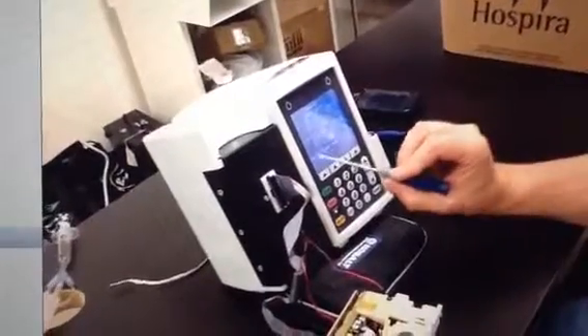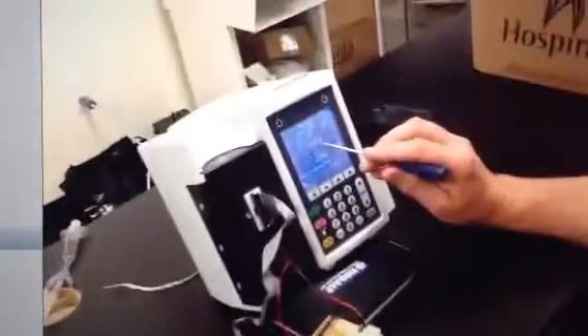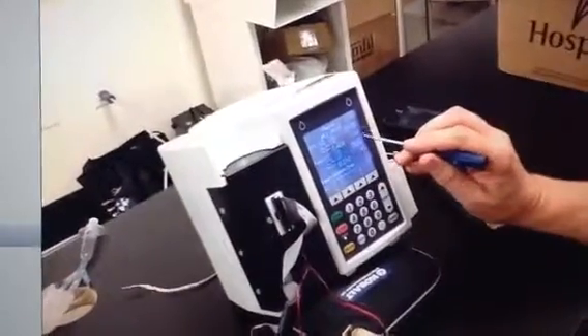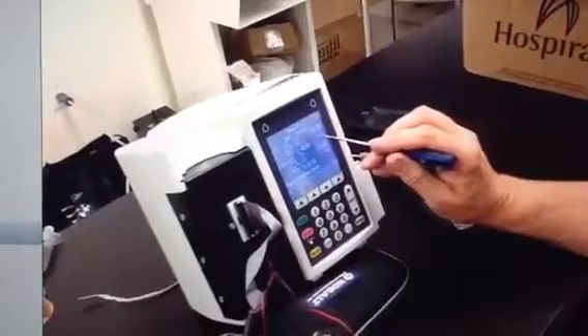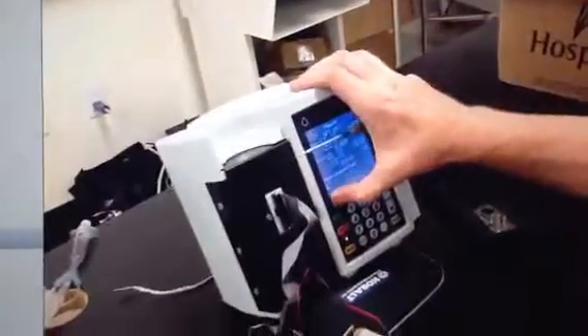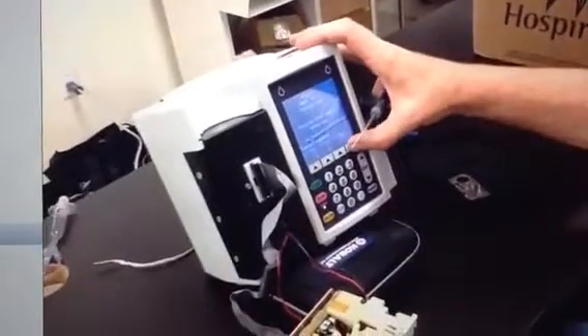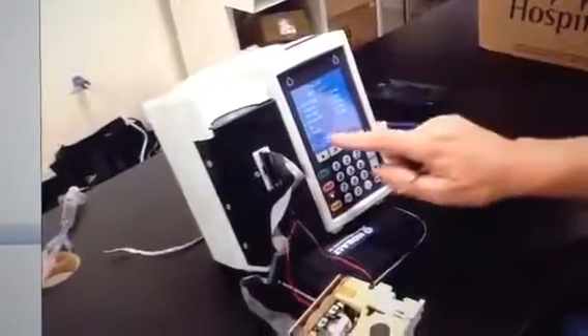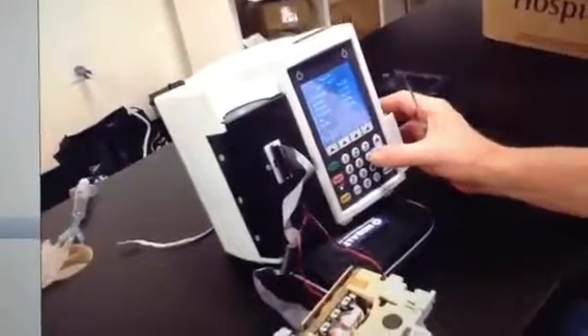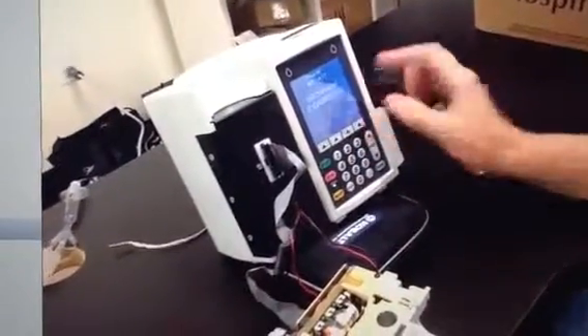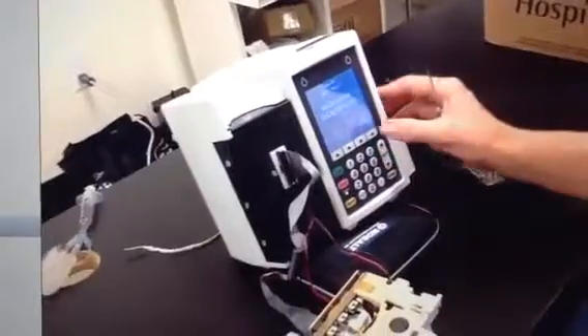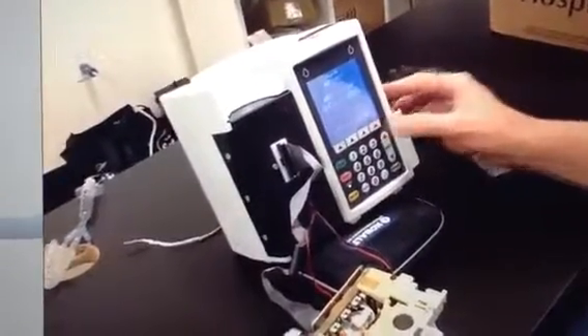Now it asks us to open the cassette door, and if we've done a good job calibrating the mech, this value will be less than this value. And we can click set, done, back, and then we verify it with the number 6. And it says mechanism is calibrated. And we click back.